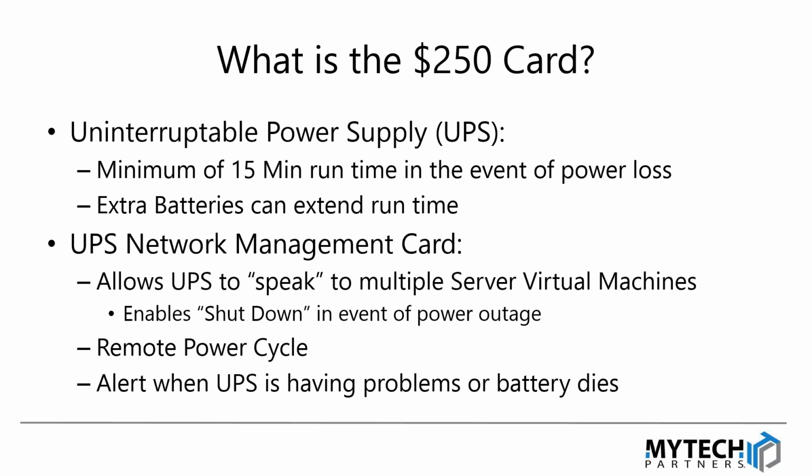So for example, if it takes 5 minutes to shut down your servers, we're going to tell the UPS, keep a runtime of, say, 8 minutes, and then if the power doesn't come back on in 8 minutes, I want you to start initiating the shutdown of your servers so that they can be sure that they're shut down before the power actually drops off and the battery runs out.